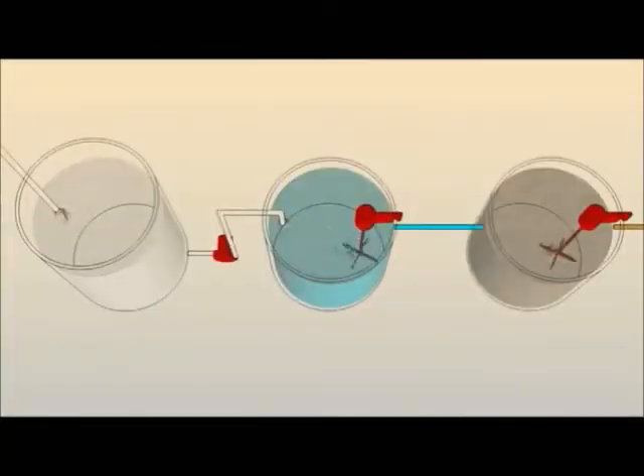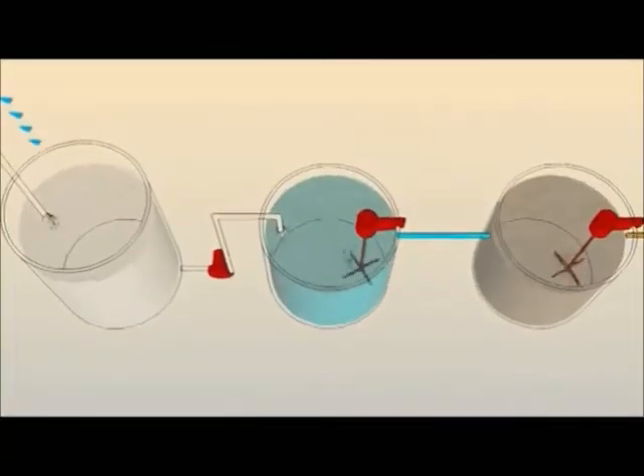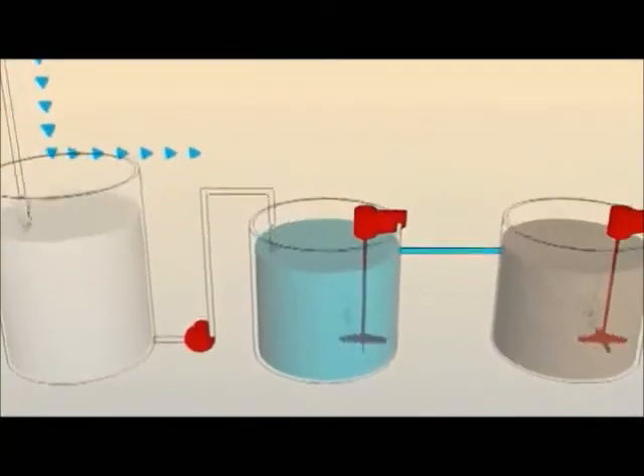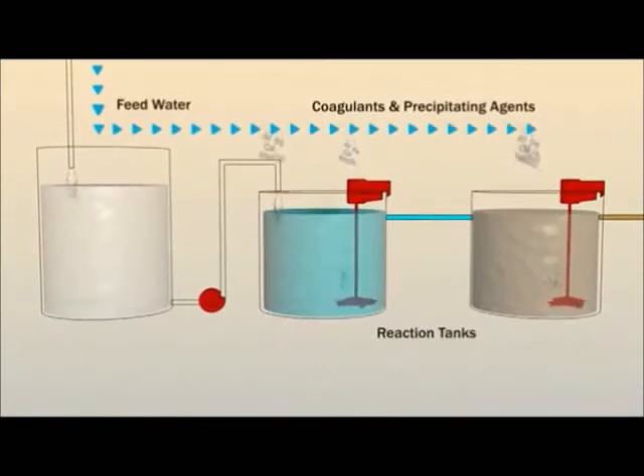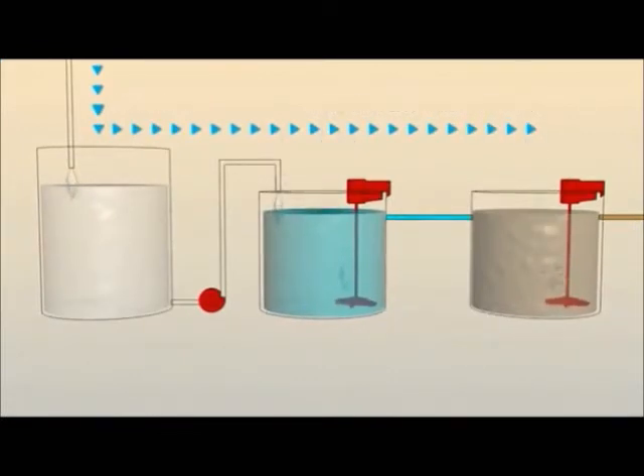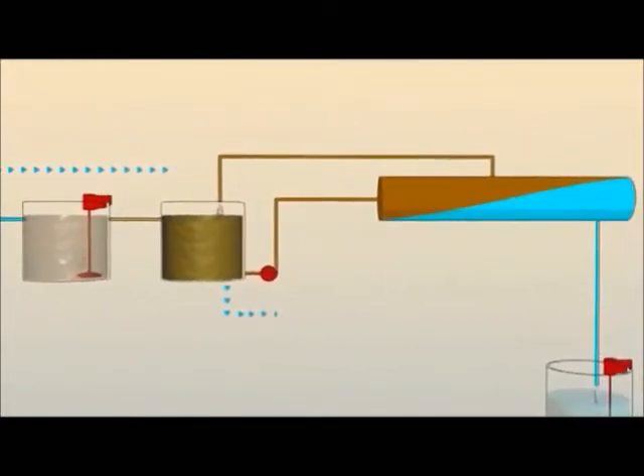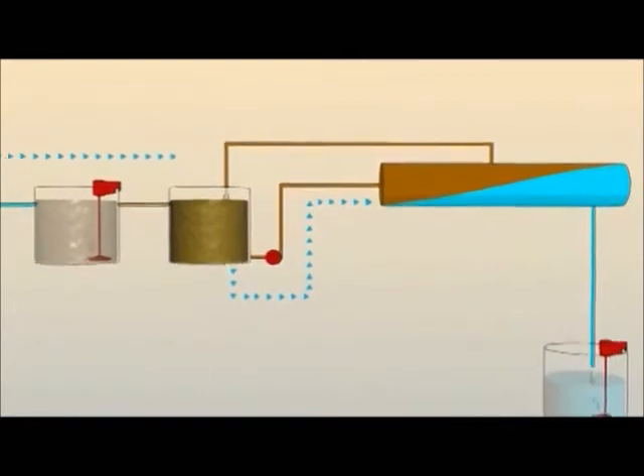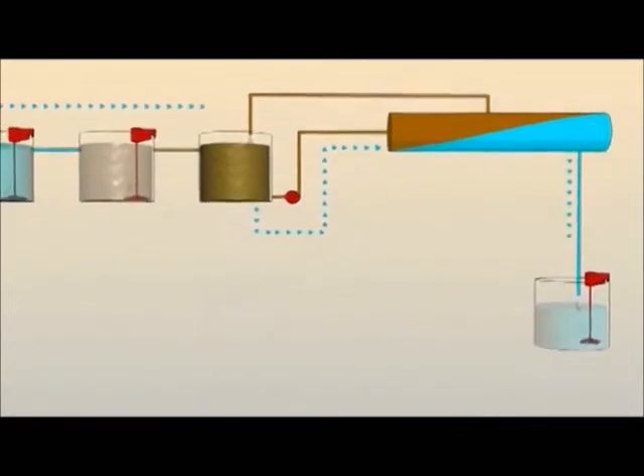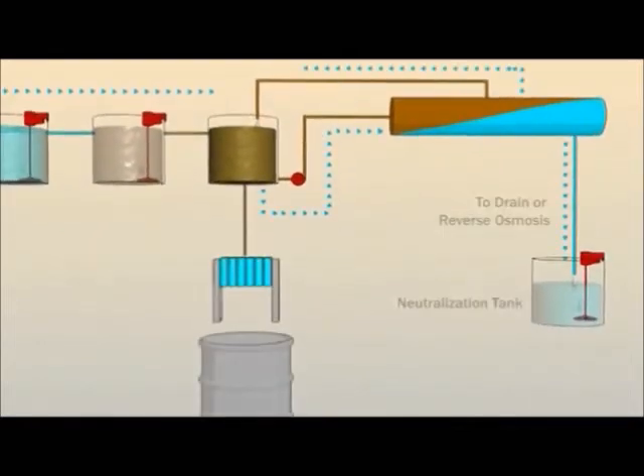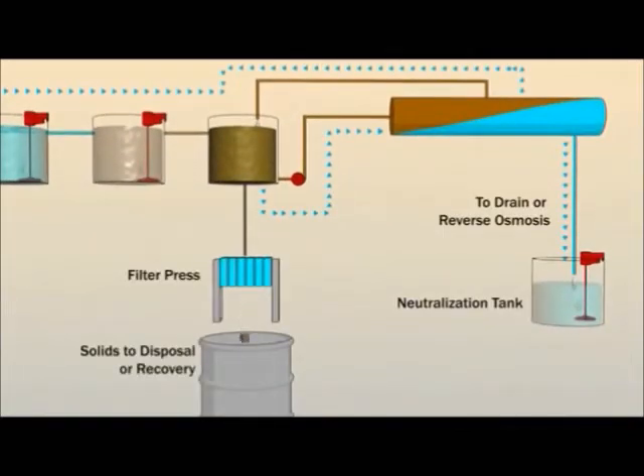In an overall filtration system, the feed water flows to the reaction tanks, where chemistry is added to precipitate contaminants and condition the water for filtration. The water then flows to the feed tank, where it is pumped to the filter modules. Clean water is removed by the filters and the contaminants return to concentrate in the feed tank.